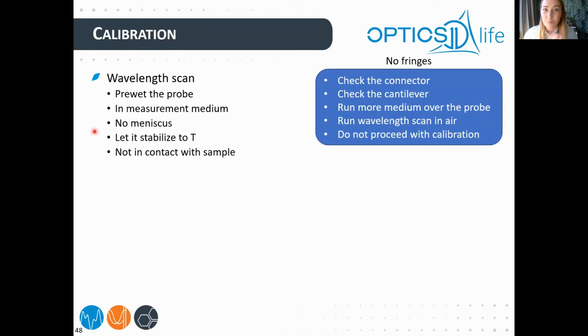Also, you need to let the probe stabilize. I'll show later how the drift looks. If you just submerge in the medium and do the wavelength scan right away, you will get the wavelength scan. However, your signal is going to drift away, and the settings that you got will be wrong, and you will have issues. You'll have to redo the wavelength scan. Also, the probe and the sample must not be in any contact. As I said, it should be in a completely neutral position.